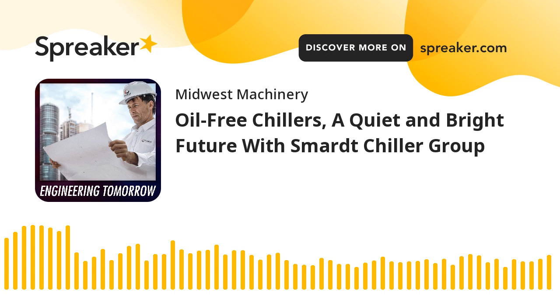I can see a future where there's no reason for all chillers to not be oil-free technology - there's simply no need to put oil into the machine. It's actually a negative in the sense that it lowers efficiency. Your payback on an oil-free machine is almost always less than 5 years, and because the equipment's life is arguably 25 to 35 years, that payback to the owner is significant. So there is a premium on first cost for that efficiency - there's no way around it, the technology demands it.